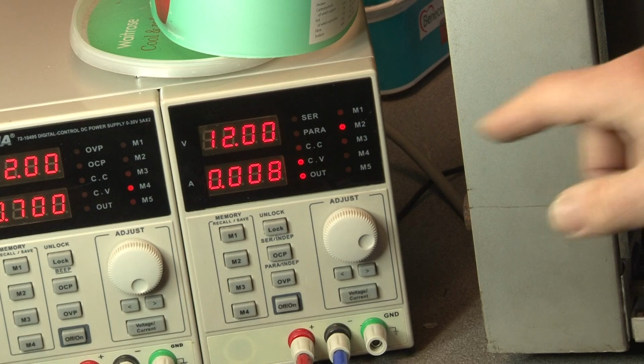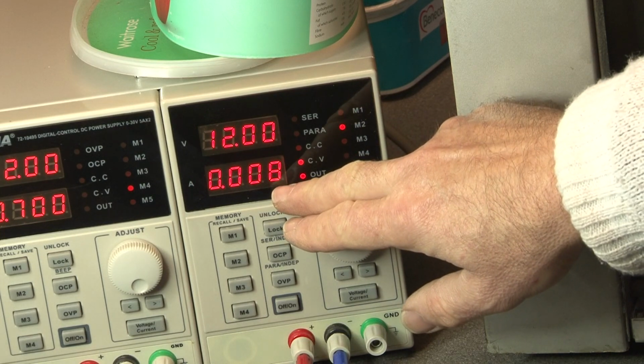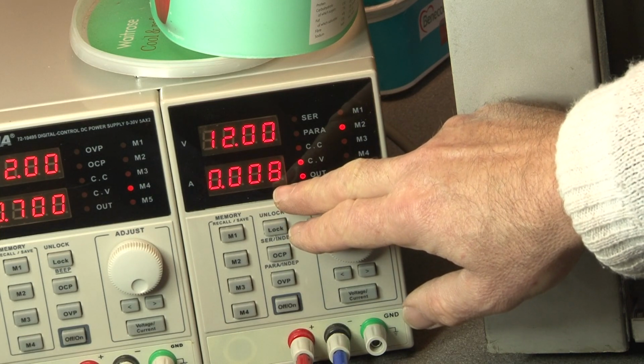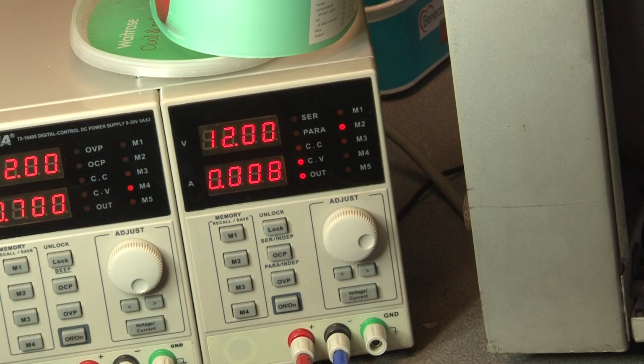You can see that the current settles to a value of around 8 milliamps, showing that there is a fair amount of leakage on this pair of capacitors. Bearing in mind they are over 50 years old, maybe that's not surprising. I'm going to have a little think about whether this is an acceptable value.